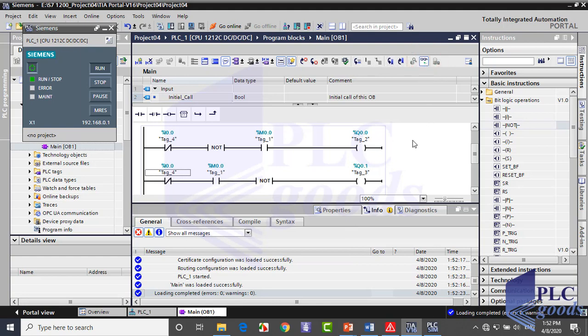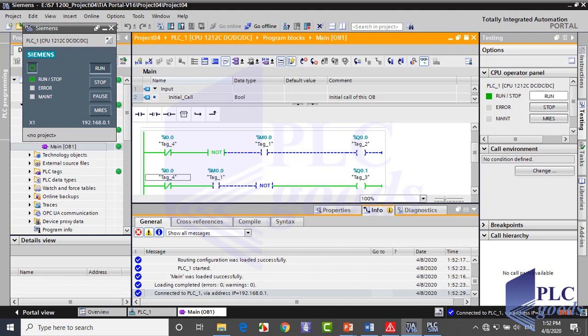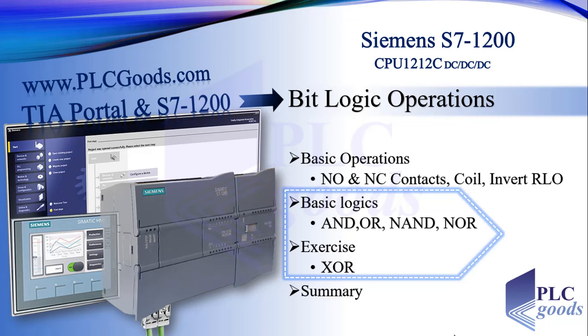Let me activate this to see my program in the CPU. In ladder language, RLO is our virtual power, and the NOT instruction inverts it. As you see, in the first line the virtual power has reached the NOT instruction, so after that we don't have it and the output will be off. In the second line, the virtual power has not reached the NOT instruction, so after that we have virtual power again and the output will be on. Note that if we change the instruction sequence in ladder language, it could change the final result too. We've learned some basic operations. In the next video, we'll see how basic operations can be combined to have basic logics in ladder language, and we'll see basic logic instructions in function block. After that, the XOR logic will be written as an exercise.